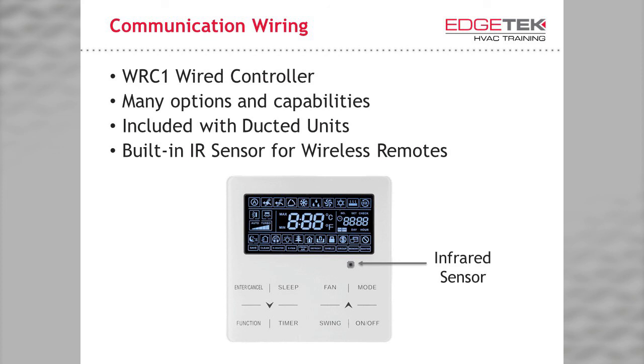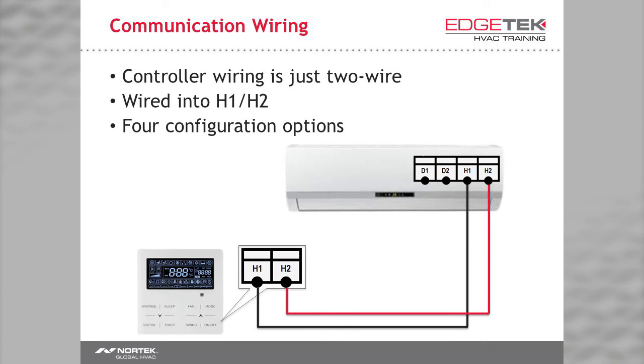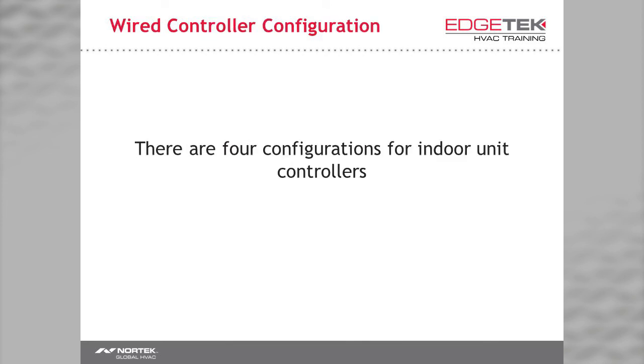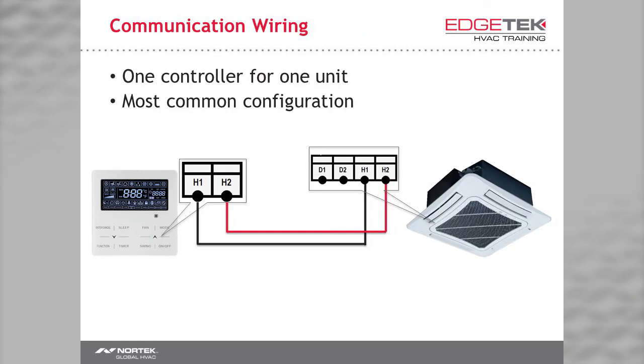This controller can be used with all of our VRF indoor units. These controllers wire into the H1 and H2 terminals on the indoor units. You're using the same 18-gauge stranded, non-shielded 2-conductor wiring you used for the main comm line. You can install these controllers in one of 4 different ways. The most common option is to wire one controller for one indoor unit.